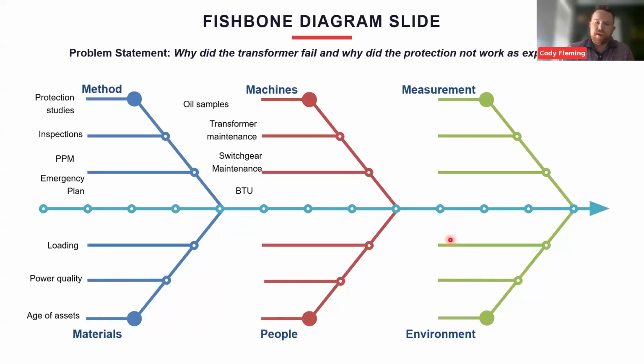So, oil samples, how deep are those oil samples going? Are you doing just fluid analysis, or Daniel, do they do DGA on these as well? Are they looking for acetylene, propane, anything like that? Good point. Touched on the transformer, Nick, go ahead, please. Yeah, that is so common. Like you say, if you're just getting fluid analysis done, you probably wouldn't have DGA, which would give you an indication of something not being right inside. We'll cover it, but for the other samples, it was a full suite, so it was your standard fluid analysis and DGA as well.